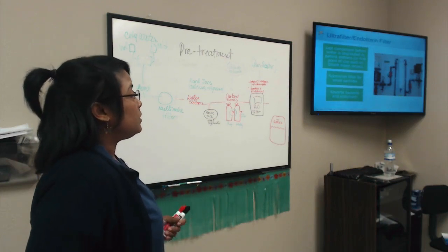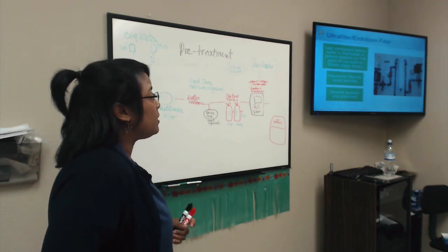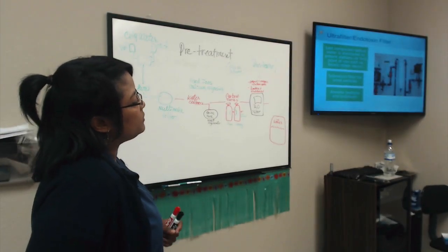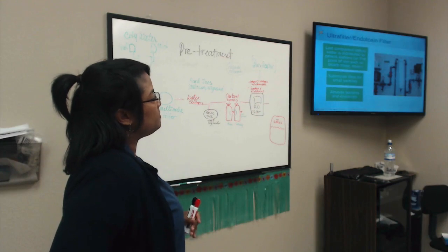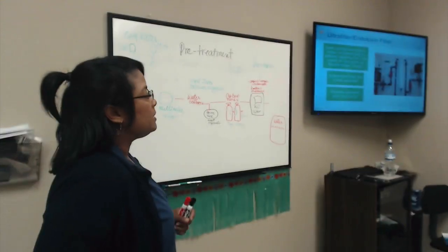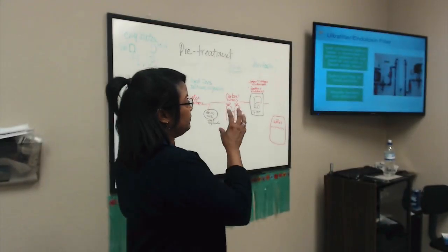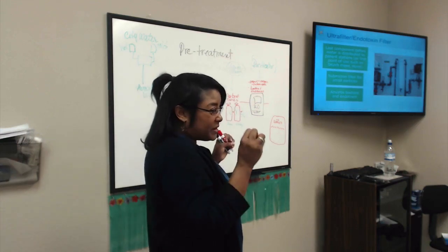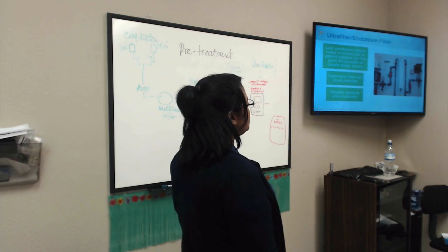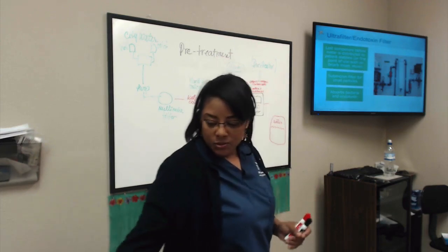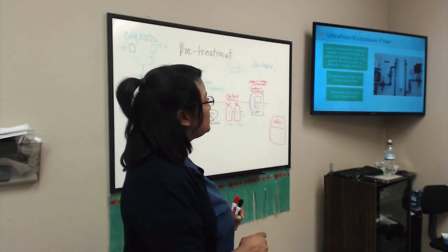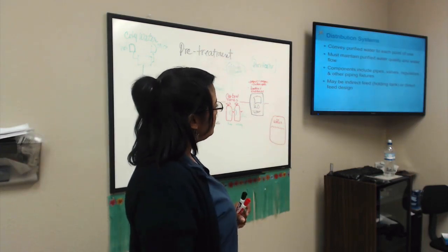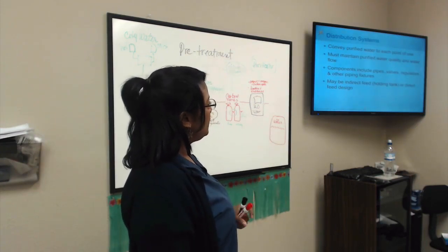So it's the last component before the water is distributed to the patient station, or the first point of use, such as a bicarb mixer, reuse, whatever. It's a filter that can filter submicron particles, and it absorbs bacteria and endotoxins. So it's an ultrafilter, for really small contaminants.